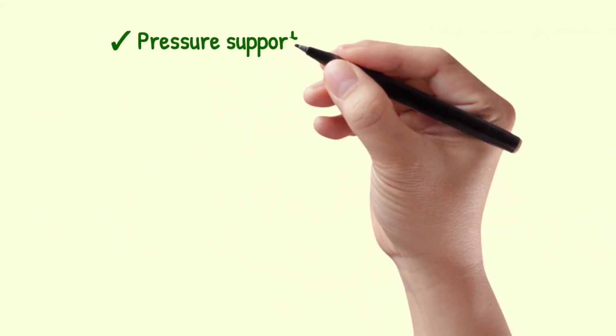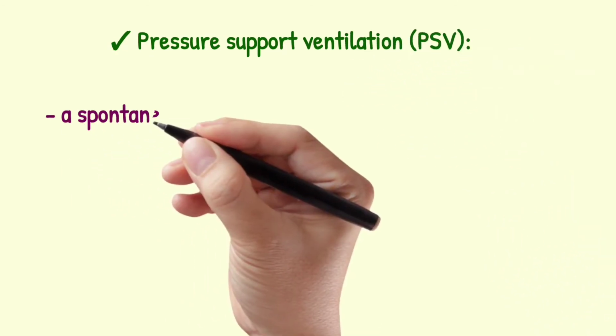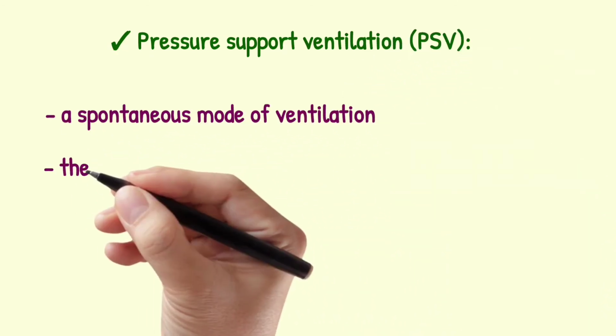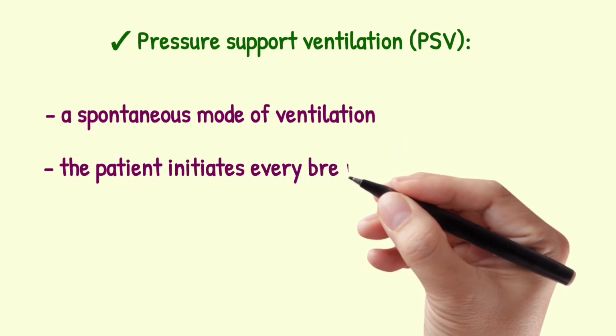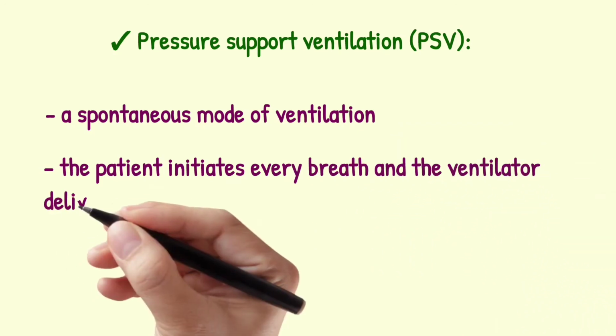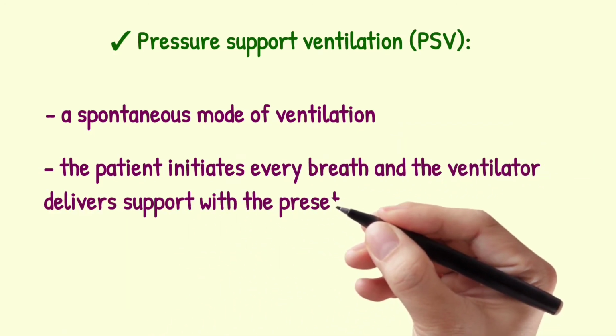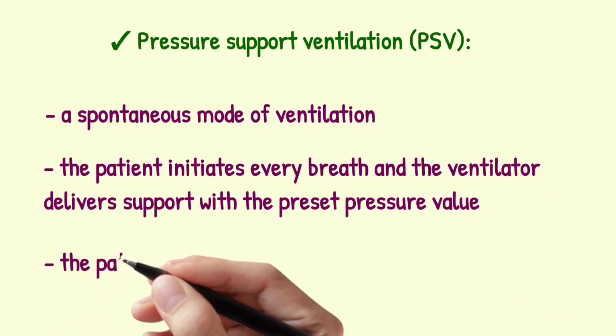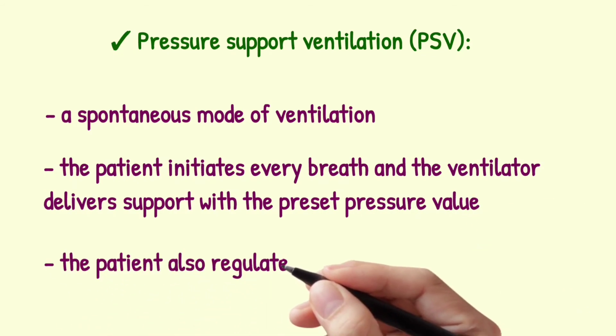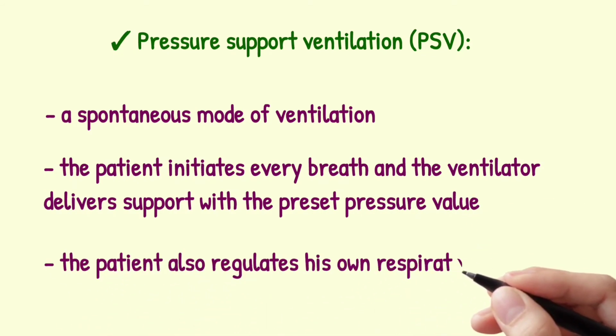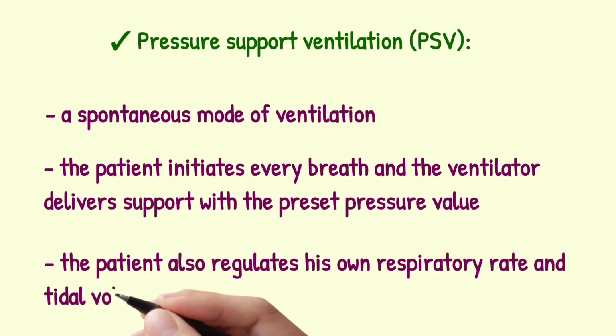Next is pressure support ventilation. PSV is a spontaneous mode of ventilation. In this mode, the patient initiates every breath and the ventilator delivers support with the preset pressure value. And with support from the ventilator, the patient also regulates his own respiratory rate and tidal volume.